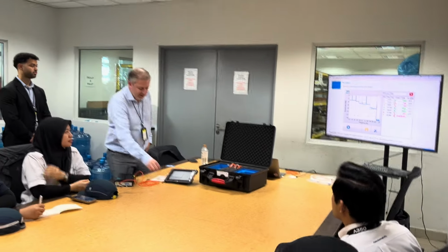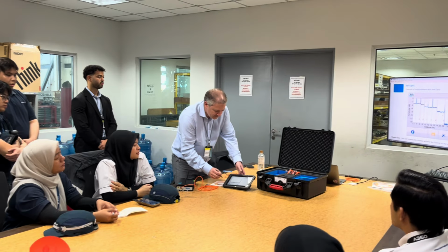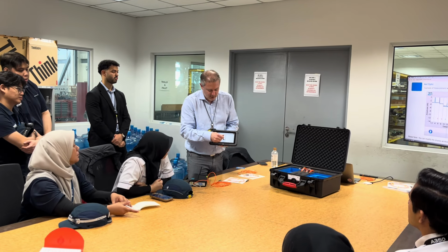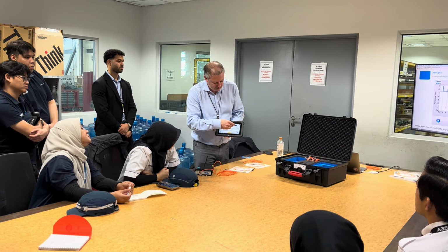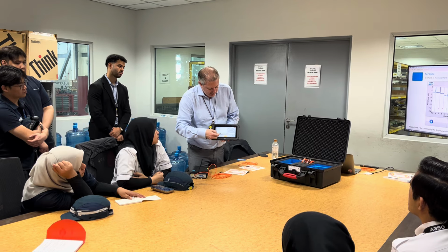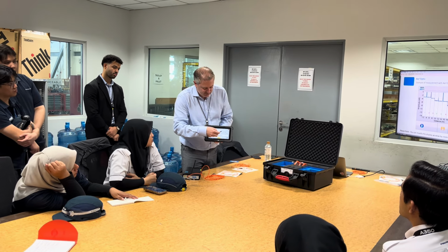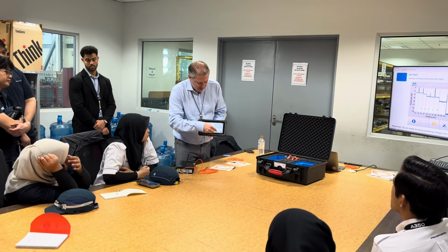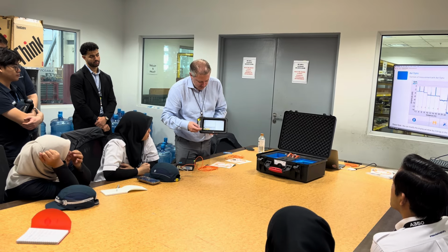So if I launch the test here, I just need to make sure I put the proper parameters. Remember, 20 meters, and we check whether it's good or not. Maybe I'll change that. Insertion loss limit is 0.2. I say OK, and then now I can launch it.